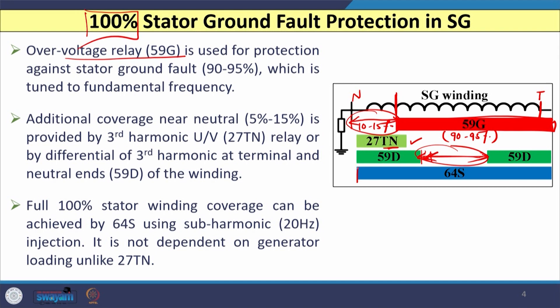To achieve 100% protection against stator ground fault regardless of loading, most utilities now use the scheme based on 64S, which provides 100% stator winding coverage using the sub-harmonic injection principle. Unlike 27TN, whose performance is affected by generator loading, 64S does not depend on generator loading — its performance remains unaffected — and provides 100% protection against ground faults at any location from terminal to neutral.